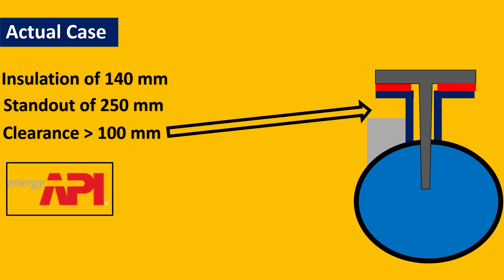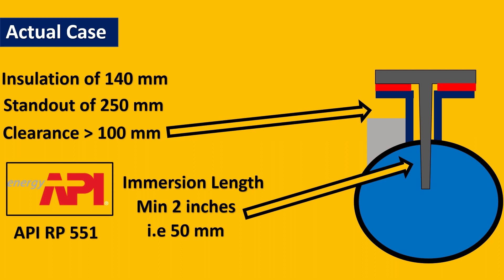So let us maybe choose the API criteria here. So the API RP said the minimum immersion length should be 2 inches, right, 50 mm. So here we will keep this as 50 mm. So my final U-length calculation is going to be 250 mm which is the nozzle standout plus 50 mm which is my immersion length. So my total U-length comes out to be 300 mm.